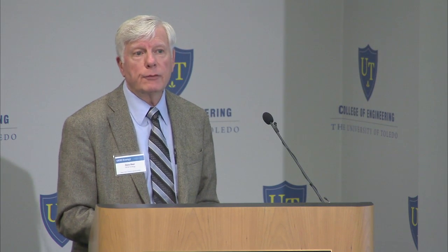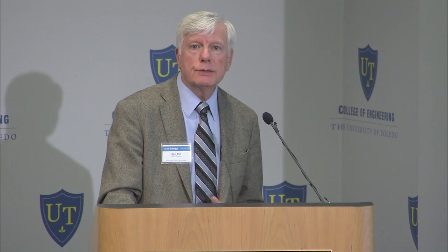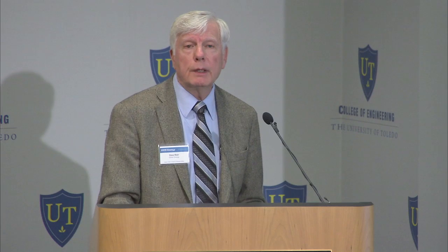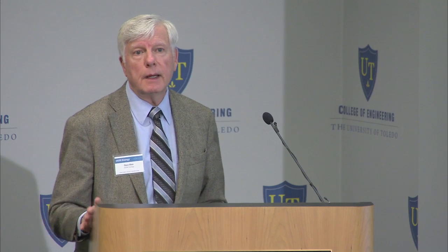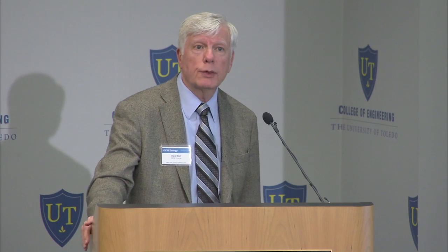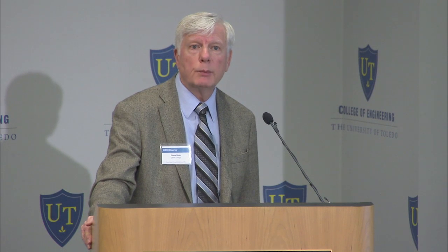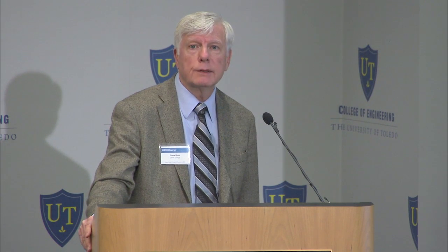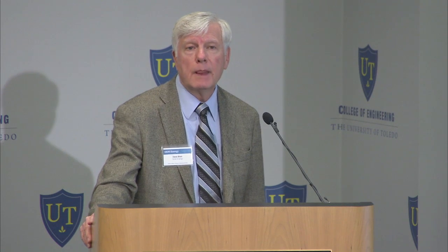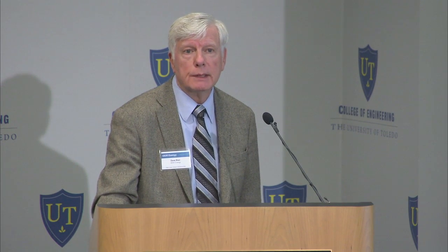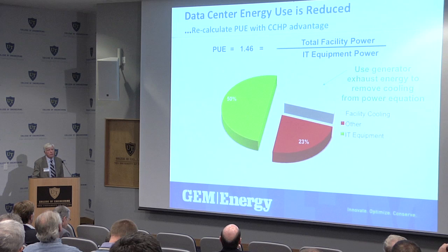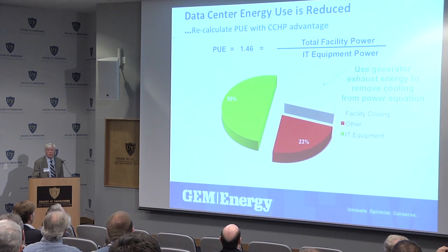In other words, if 4 out of 5 generators are used to run the data center, we could operate the remaining generator and send that electricity somewhere else, using some of our redundancy. Yet if the non-critical load becomes expendable and the data center becomes the priority, our reliability stays very high, but the opportunity to recover energy is still there. So this PUE can be driven even lower by looking at more and more of the details.